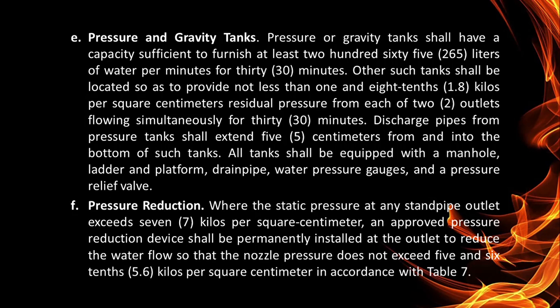So, pressure and gravity tanks. Pressure or gravity tank shall have a capacity sufficient to furnish at least 265 liters of water per minute for 30 minutes. Other such tanks shall be located so as to provide not less than 1.8 kilos per square centimeter residual pressure from each of two outlets flowing simultaneously for 30 minutes. Discharge pipes from pressure tank shall extend 5 centimeters from and into the bottom of such tanks. All tanks shall be equipped with a manhole, ladder, and a platform, drain pipe, water pressure gauges, and a pressure relief valve.